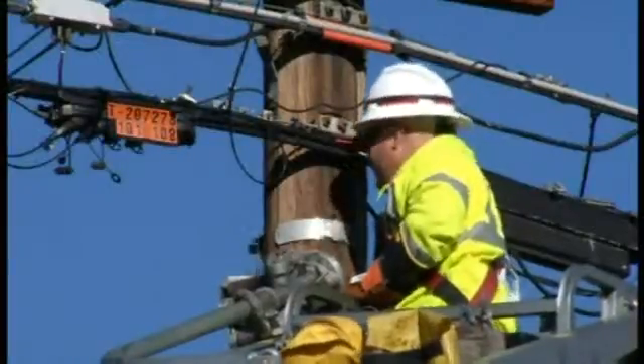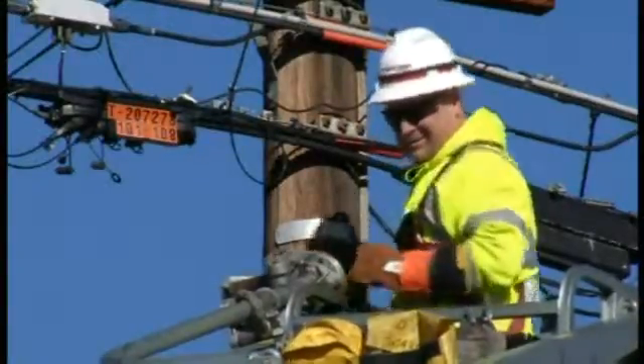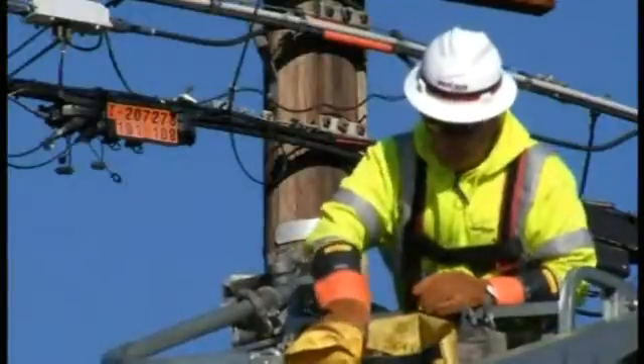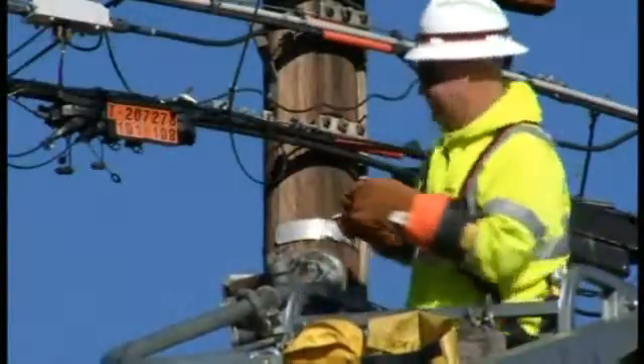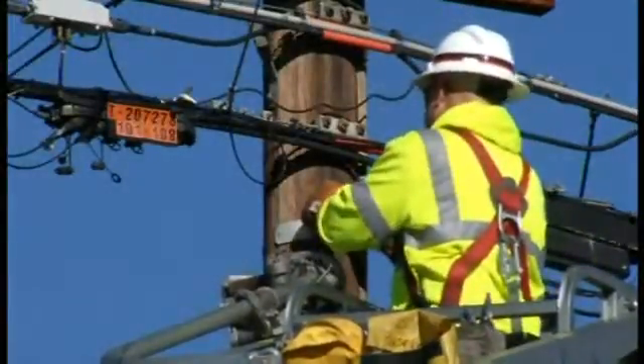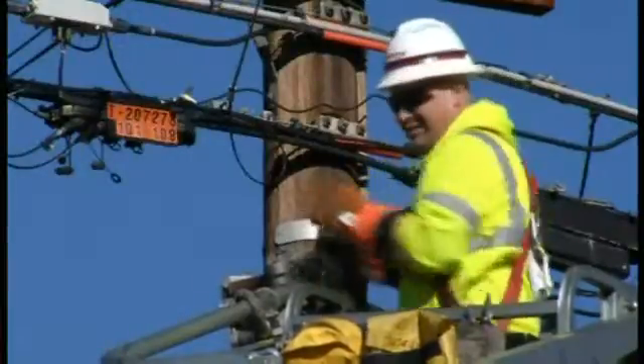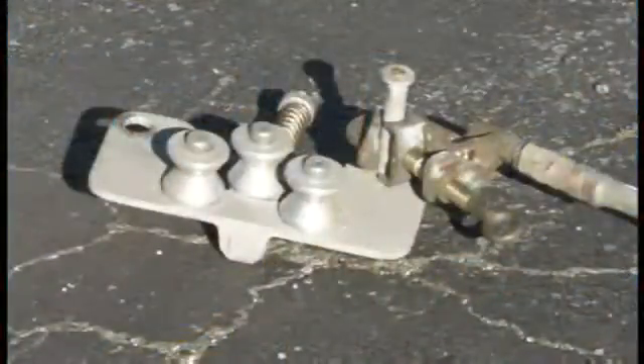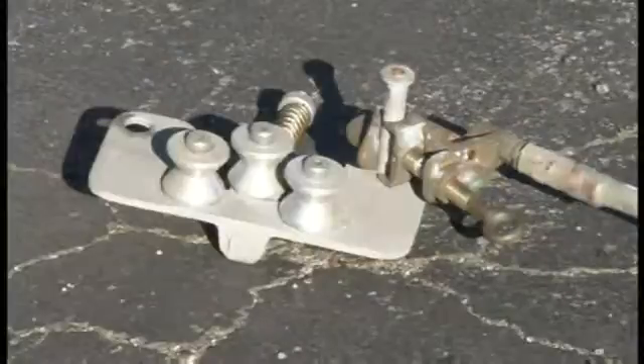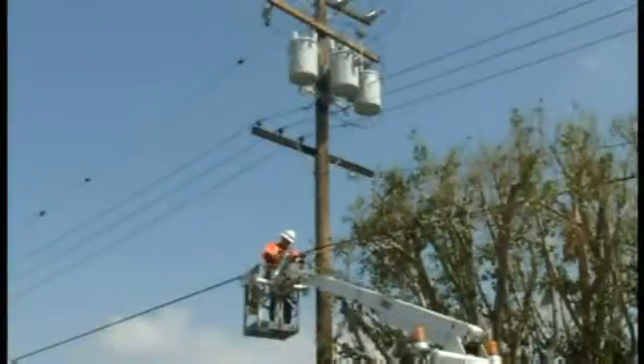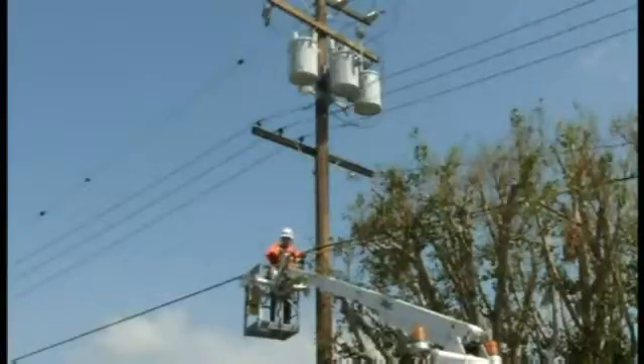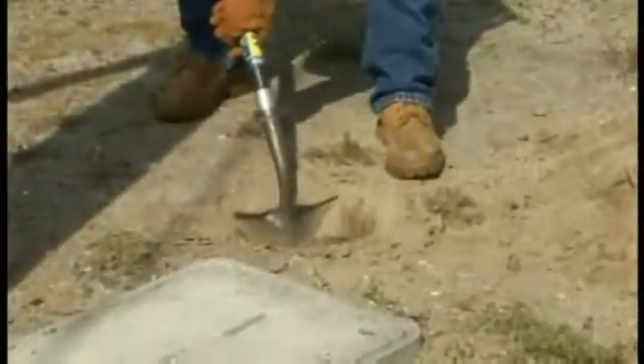Whenever contact with electrical power is possible, this includes whenever placing or removing strand. Insulating gloves must be worn until the strand is tensioned and dead-ended. In this instance, the gloves are worn, and a grounding strand roller must be used as well. In addition, insulating gloves must be available in the bucket of an aerial lift whenever the lift is occupied and/or used.